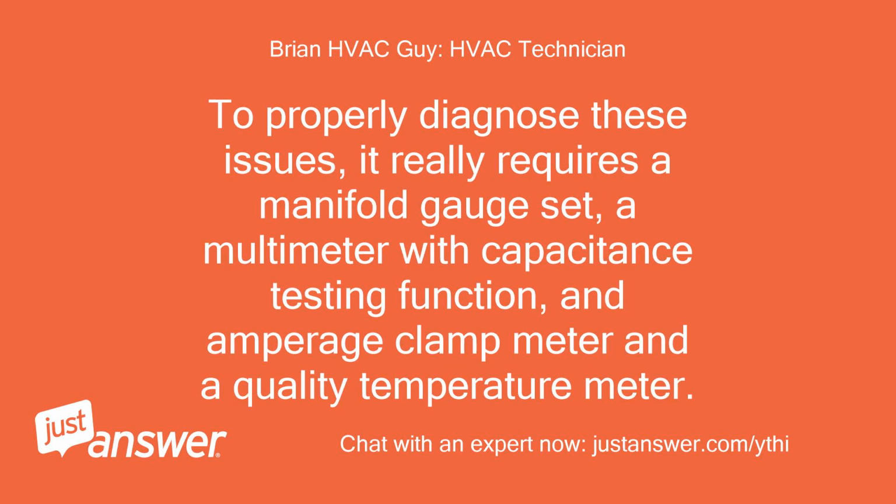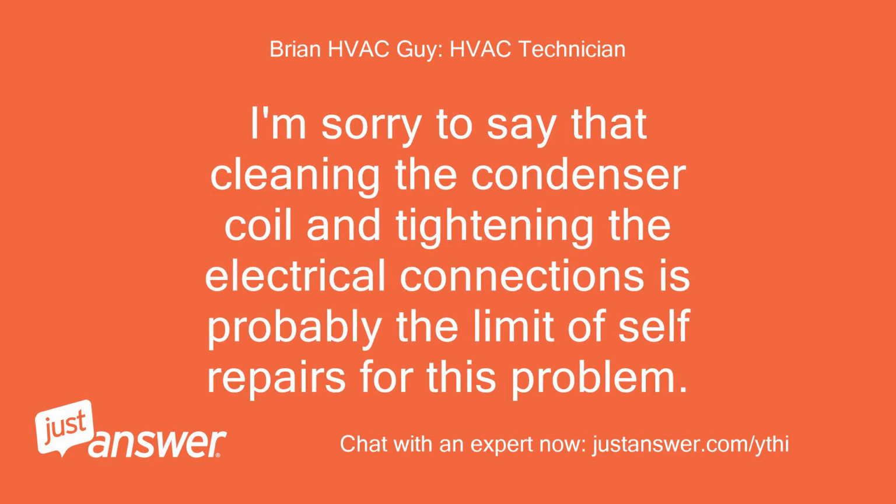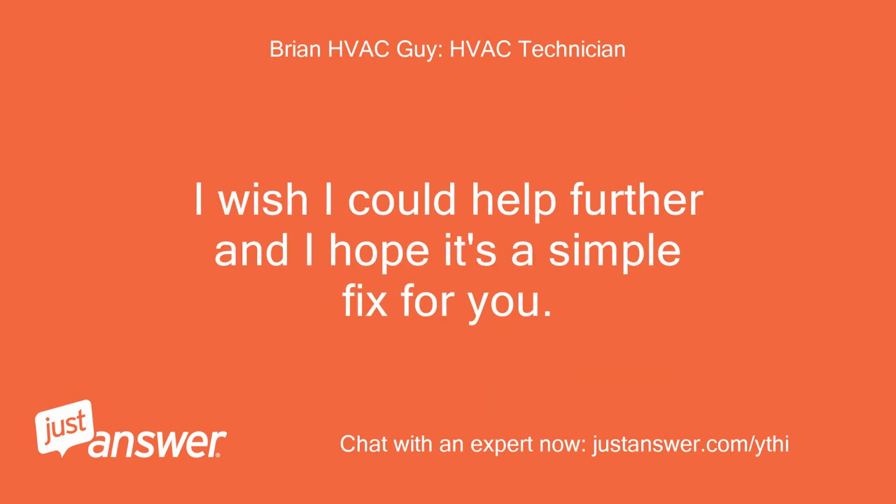To properly diagnose these issues, it really requires a manifold gauge set, a multimeter with capacitance testing function, an amperage clamp meter, and a quality temperature meter. I'm sorry to say that cleaning the condenser coil and tightening the electrical connections is probably the limit of self-repairs for this problem. I wish I could help further, and I hope it's a simple fix for you.